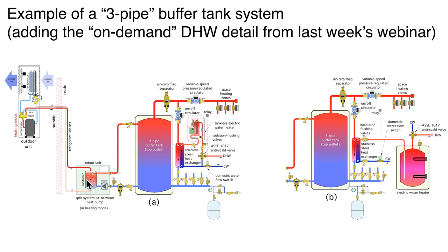Then we're putting that heat back into the tank. The Argosy tank does have a nice inch-and-a-quarter takeoff up on the top, so we're pulling the hottest water directly off the top of that tank. Showing another air-and-dirt separator here, and we've got a couple of pathways — a variable-speed, pressure-regulated circulator going off to some zone valves, or other valve-based zoning like thermostatic radiator valves.